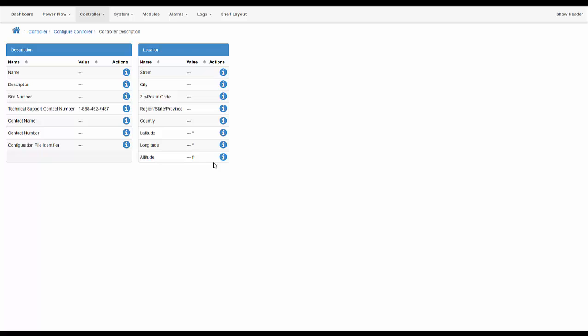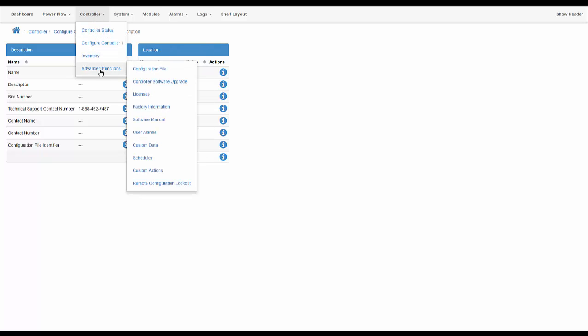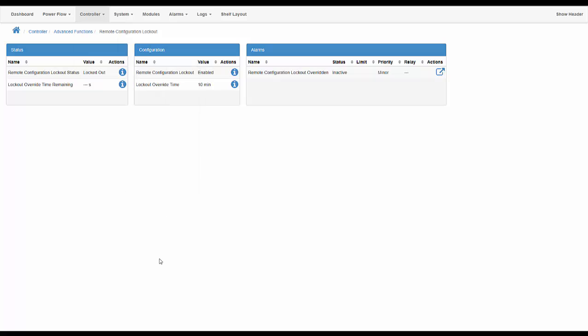The override on the LCD will, by default, allow access via the web interface for 10 minutes, which is a configurable time value. To get access to this configuration, you go to Controller, Advanced Functions, Remote Configuration Lockout. As you can see, it is enabled, and I am unable to make any changes here.